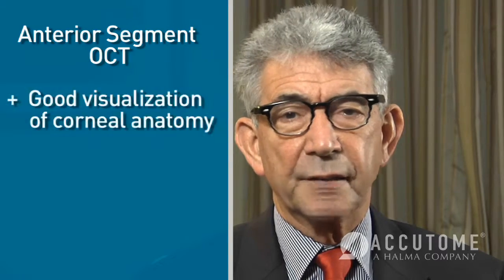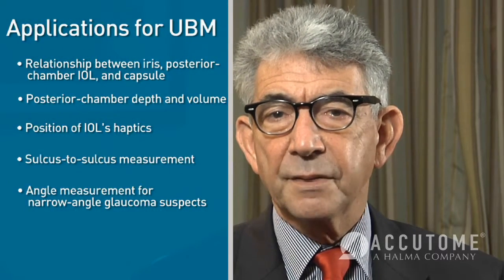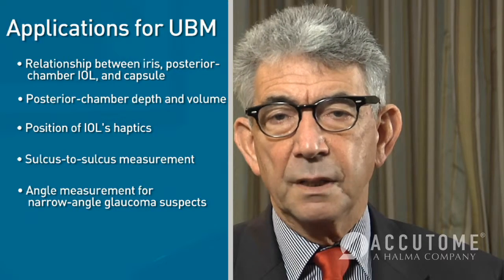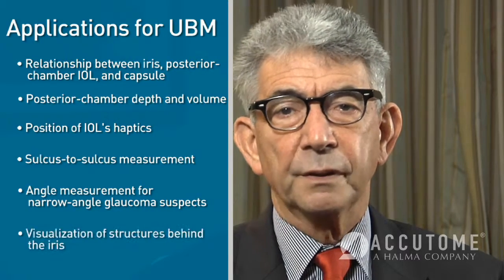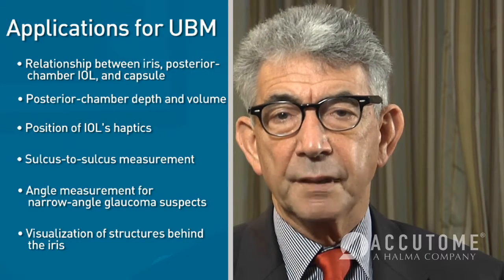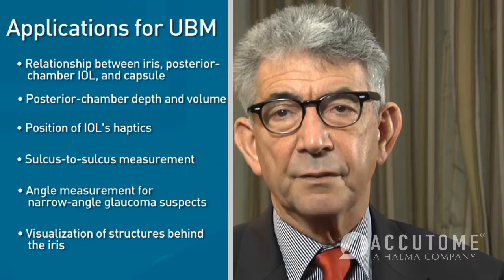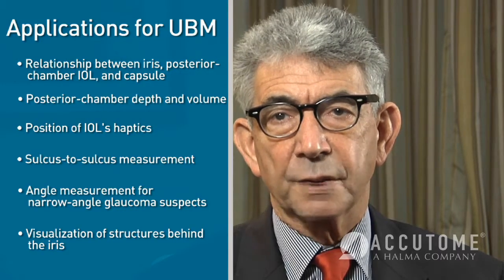The anterior segment OCT device and the UBM differ in certain ways. OCT gives very good definition of corneal anatomy and architecture. The main problem with OCT, however, is that one cannot image behind the iris. The UBM is therefore essential for posterior chamber relationships and for anywhere beyond the iris, as OCT cannot visualize behind opaque structures.